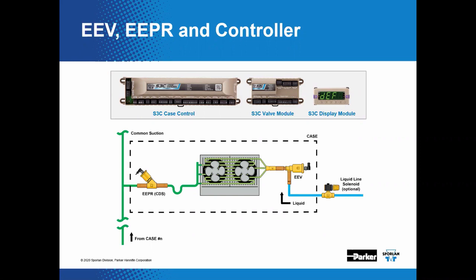What that would enable is individual control of temperatures, of course, up and down that lineup for different types of product within that lineup. And that really gives you some flexibility. It gives you flexibility, absolutely. So that's something that you should scrutinize, whether you're setting it up with a Sporlan S3C case controller or you're using some other manufacturer's device, is look for that flexibility.